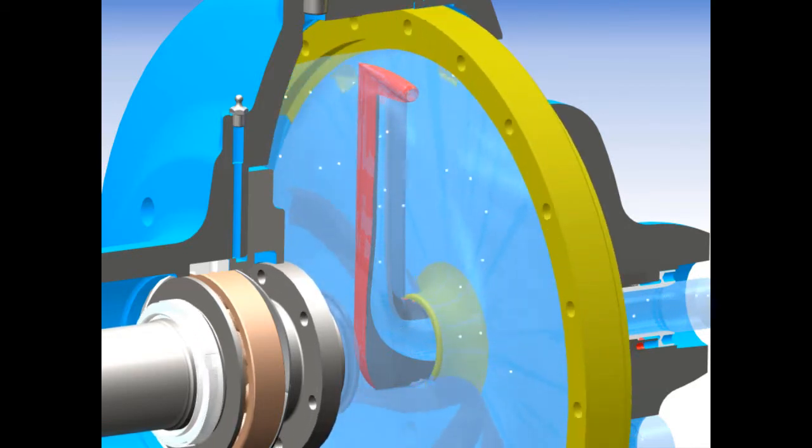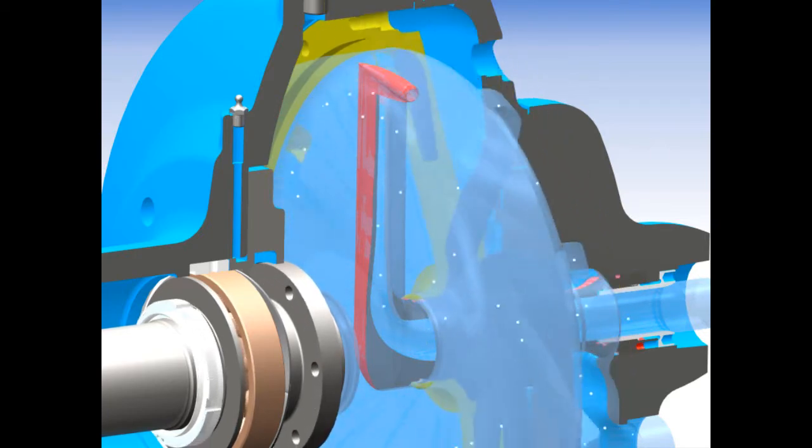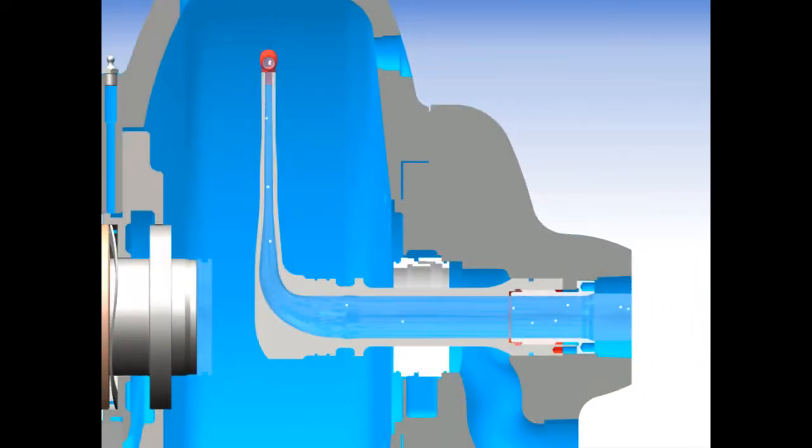The developed pressure forces the fluid down the internal passage of the pitot tube and out of the pump discharge, thus producing smooth pulsation-free flow.